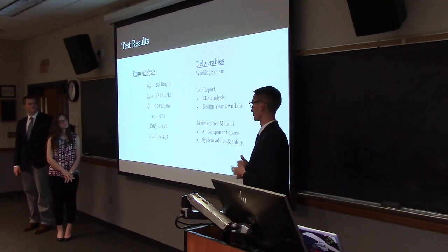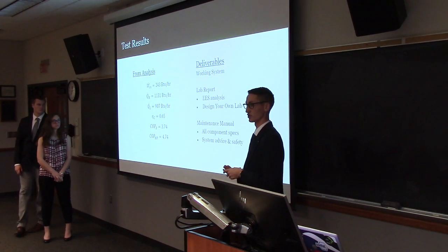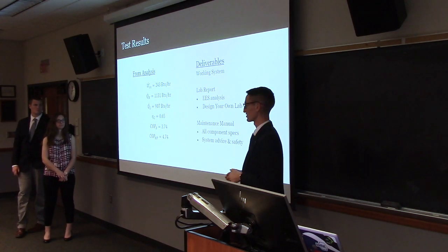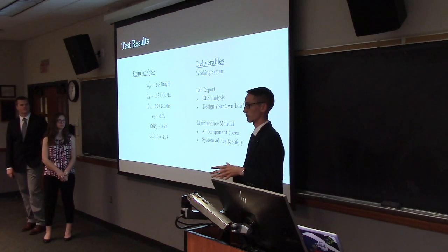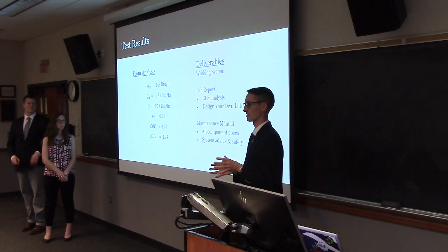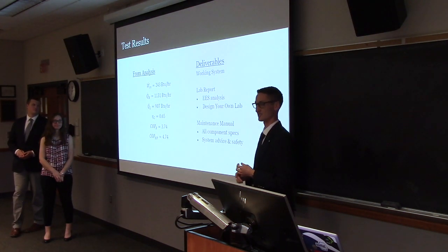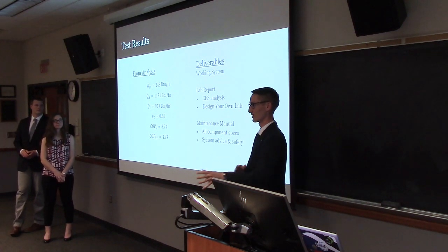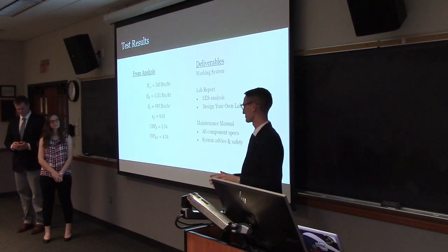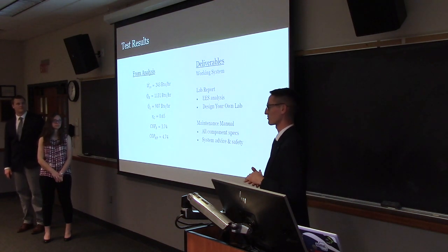And the coefficient of performance for the refrigerant side is actually very good. From the initial installation of the refrigerant, we actually had our control volume filling up with ice within the first 15 minutes. That surprised us quite a bit because the system was just running very well. A little too well actually for the time space, but we were able to make adjustments so that it wasn't freezing and it wasn't hurting our pumps.